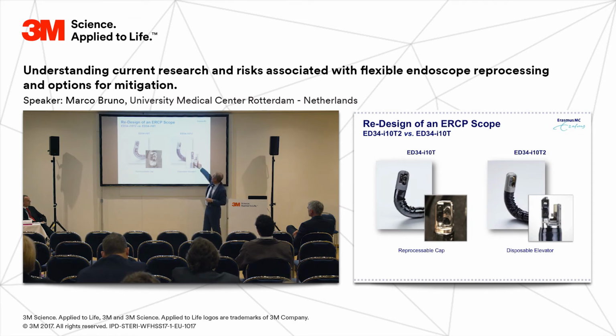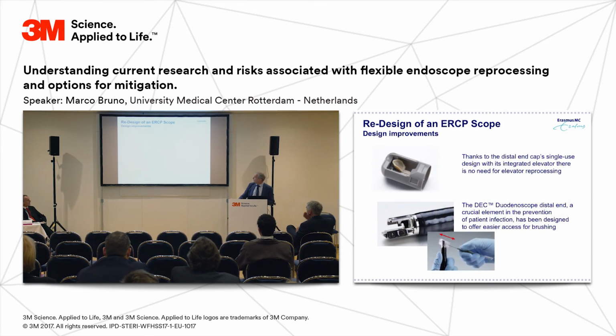But if you look at the design of the tip of this new scope and the design of the tip of this older scope, it's not very difficult to see that this one is much easier to clean. Still, it has some intricate surfaces, but this is easier to clean. You see this in more detail here. The trick is that the cap is not only removable, but the movable part of the elevator can also be removed. Then you have a much easier to clean scope where you can use brushes to reach those areas that you cannot reach in the older generation scopes.